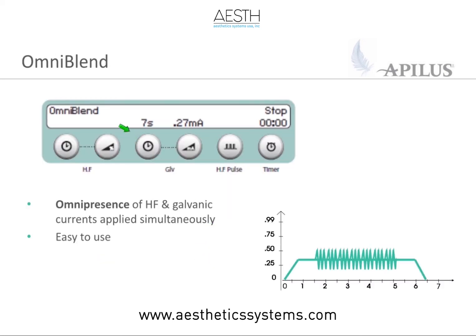The next type of blend is our continuous blend. If you look at the graph, the galvanic does the same thing. We just have 7 seconds, and in this example, it's 0.27 mA. So our galvanic ramps up, stays consistent, and then ramps down from there. What is different is how the high frequency is thrown in. In the pulsing blend method, we had the high frequency in 3 different pulses. Here it is just continuous, meaning that you will have a low-level high frequency, but it will be on for almost the same amount of time as our galvanic pulse.